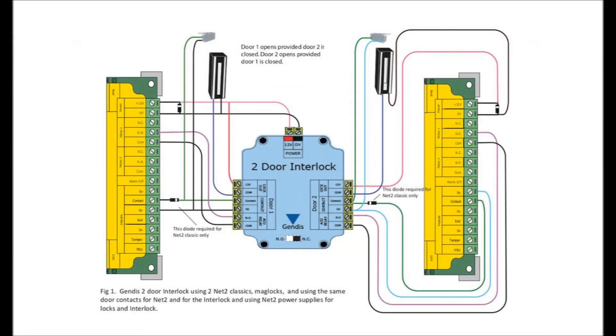You may wish to use monitored mag locks, and this is not a problem. You will need to connect from a normally closed, normally open or comm relay on the mag lock, and configure with the interlock as such that the output is closed when the door is closed.